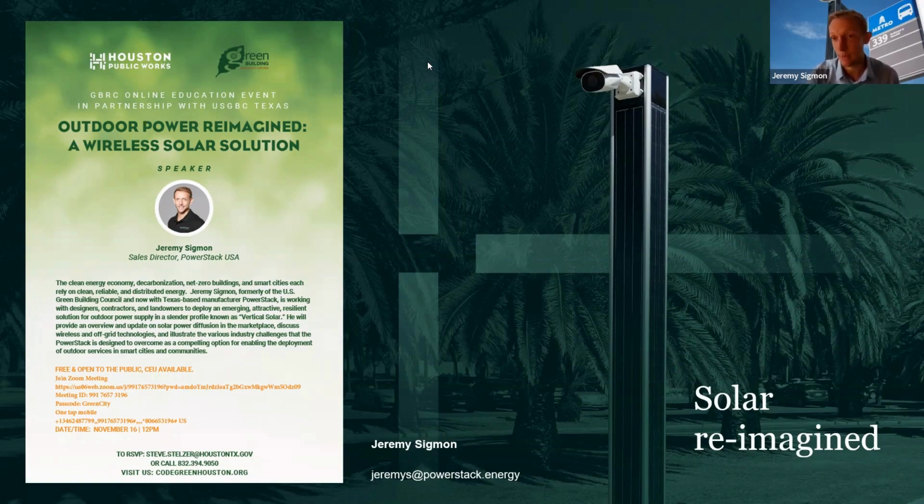Number one, there's a stack effect inside the column. The bottom is actually open air, which allows for air to flow up and past them. But we also understand from our systems that the batteries actually operate quite well at a pretty wide range of temperatures. And that stack effect is helping with convection cooling. And we run a series of insulators around those batteries, so they're actually not fully snug within the pole. They've got an insulation layer around them. And we've not found that they've been a problem.